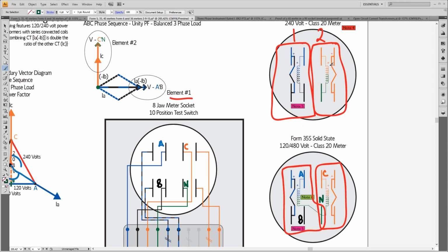Yeah, exactly. And then the other element is exactly right. It's no different than the first element here. C neutral voltage, IC current. But instead of having A to B voltage, I only have A to neutral voltage, which, like Kevin just said, is 120 volts. But in order to do the metering right, I need to have 240 volts. This is how I do the metering right.